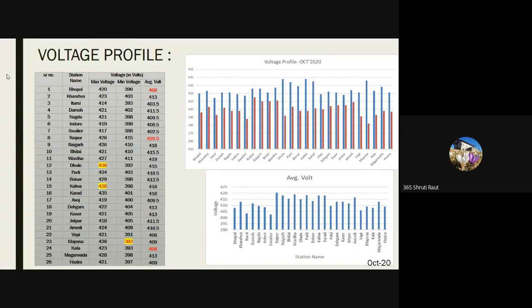But after observing the data collected from the Dhule and Raigarh representatives, the high voltage is because of reactive power compensation. So how is reactive power related to the voltage? In general, decreasing reactive power causes voltage to fall, while increasing it causes voltage to rise. When reactive power is supplied at lower voltage, as voltage drops, current must increase to maintain power supply, causing the system to consume more reactive power, and further voltage drop. So in this scenario, we conclude that when reactive power compensation is there, voltage at these nodes or substations will increase.